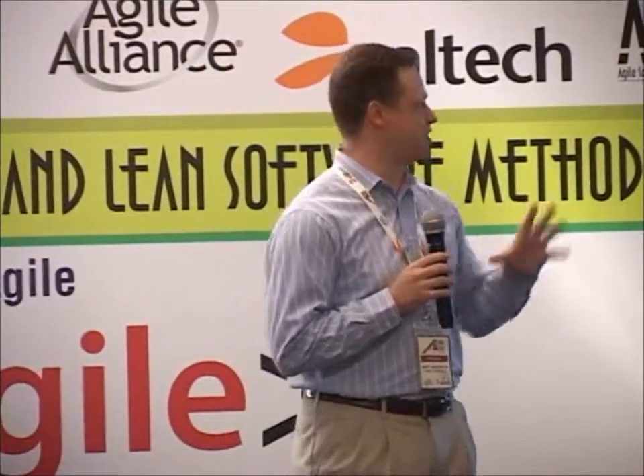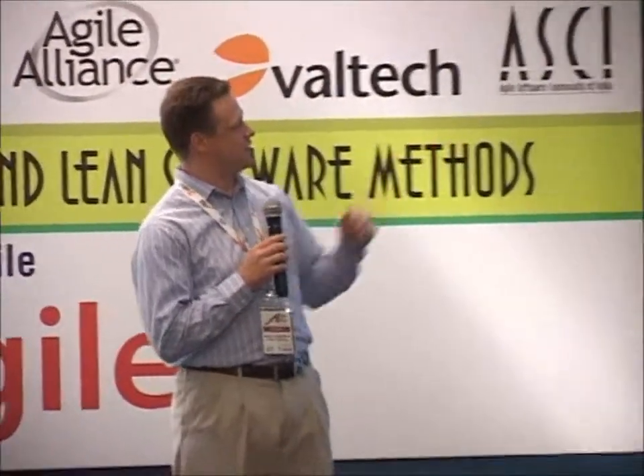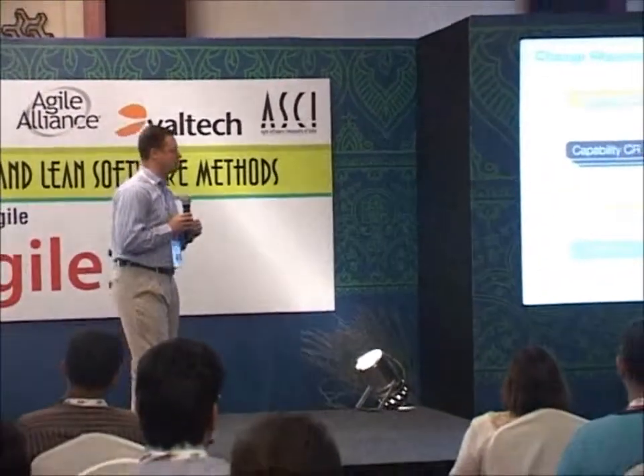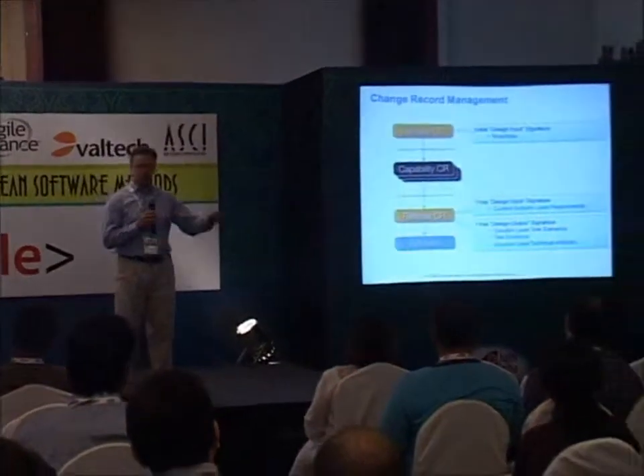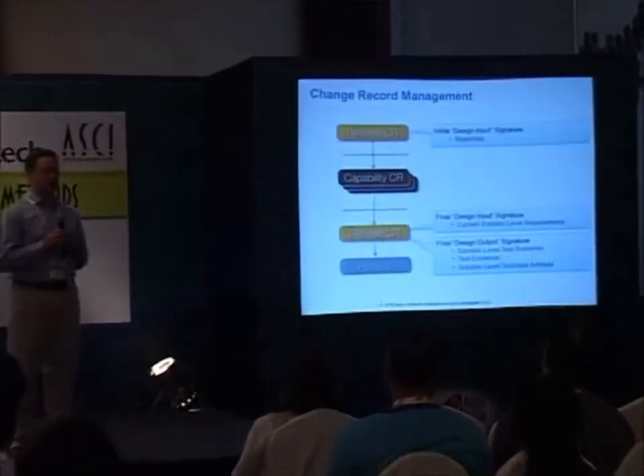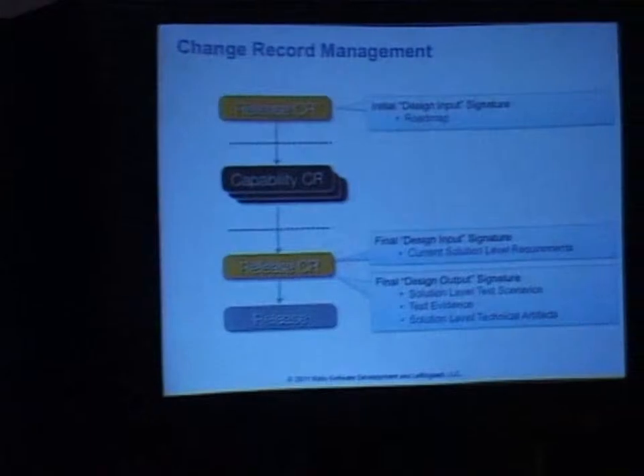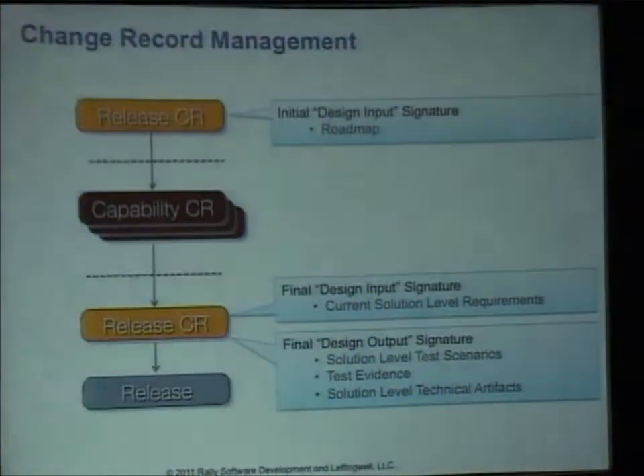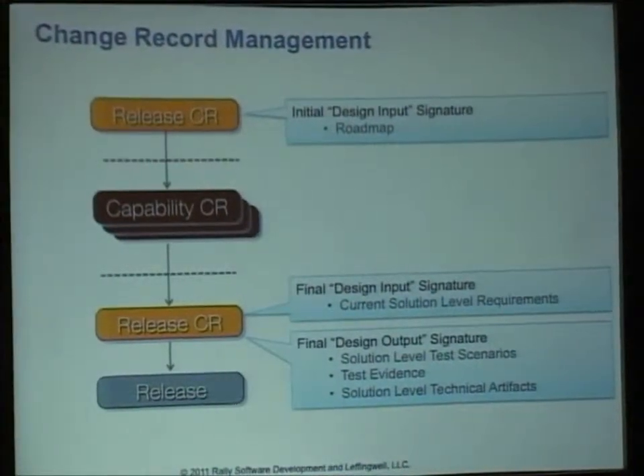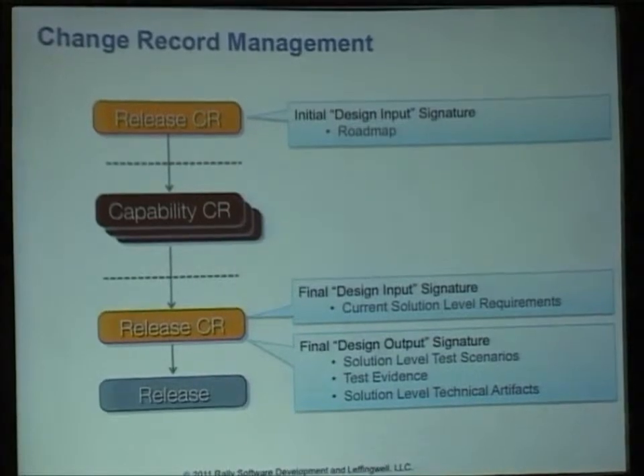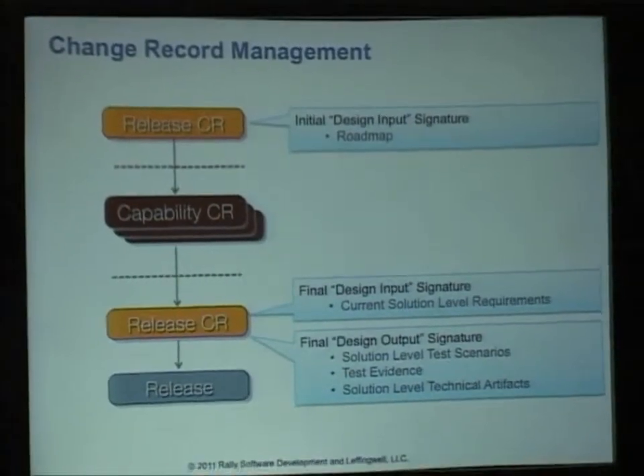So when we do any work, we look at everything as a change record. We have release change records, so we would sign off our design input at this release CR level. We would then go down, and when we're going to release, we sign off again design input, design output, and you'll see the various things we would have there: solution level requirements, our traceability matrix, whatever we choose that to be. Those are all included in those.